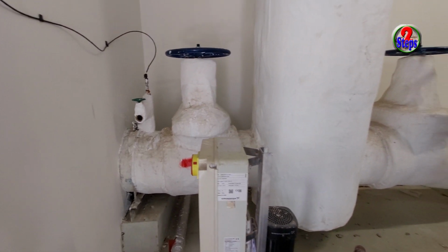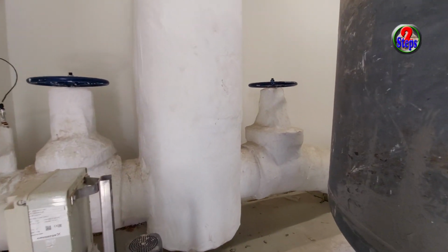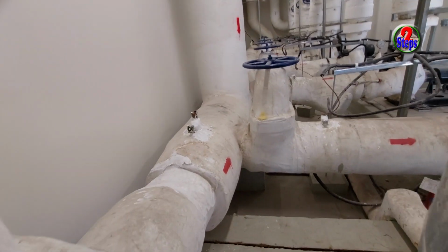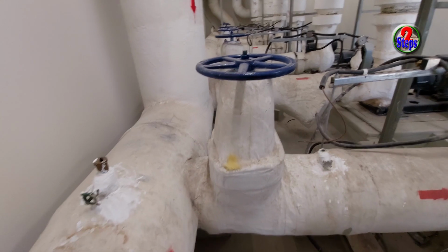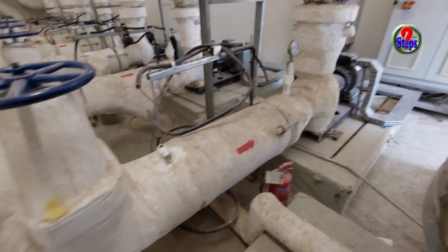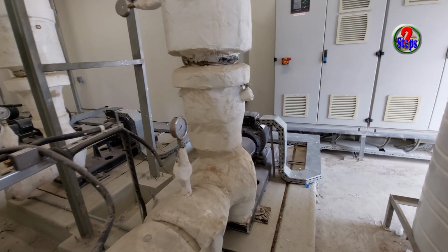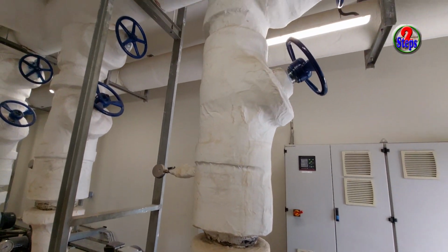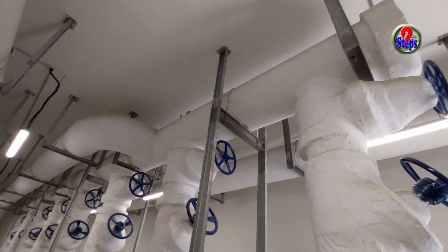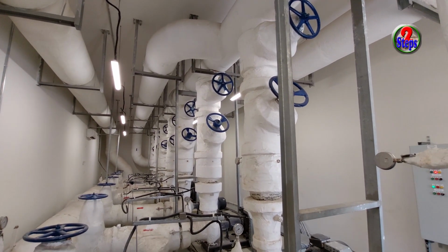Now I am inside a running pump room. Here is the main line from the domestic area. This is the air separator. Both sides have isolation valves. This one connects to the primary pump suction header. Each pump connects to the suction header typically. There is an isolation valve, strainer, pressure gauge, rubber flexible connector, then the pump. After that, the discharge line has a flexible connector, NRV, DRV, isolation valve, then connects to the discharge header, meaning the outlet header. This discharge header goes directly to the water chiller units.